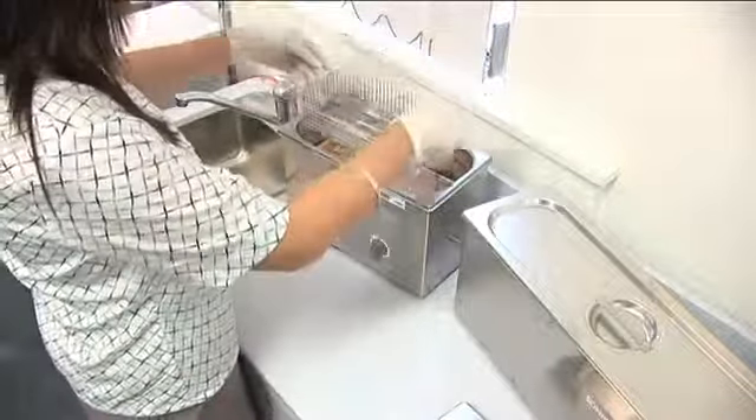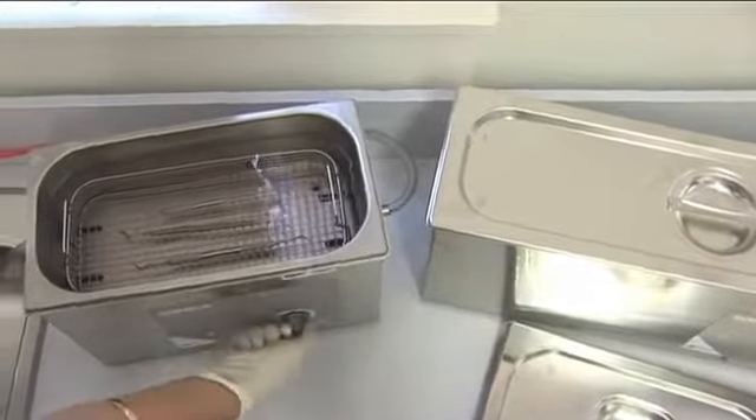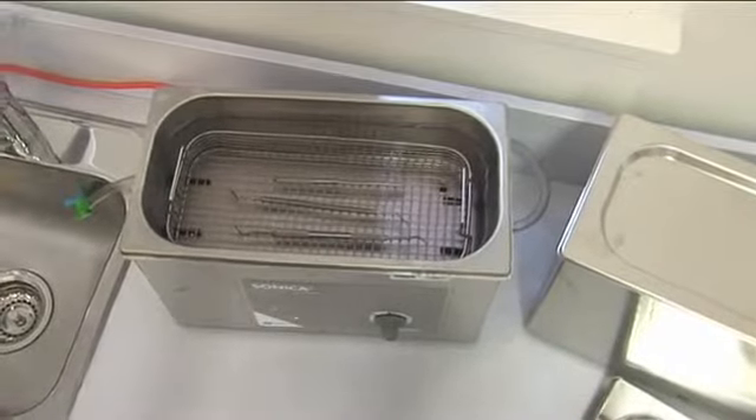Ultrasonic cleaning has long been recognized as the most effective method of cleaning and maintaining your instruments. In Soltec Sonica ultrasonic cleaners, cavitation of liquid causes microscopic implosions to occur over all surfaces of immersed instruments.